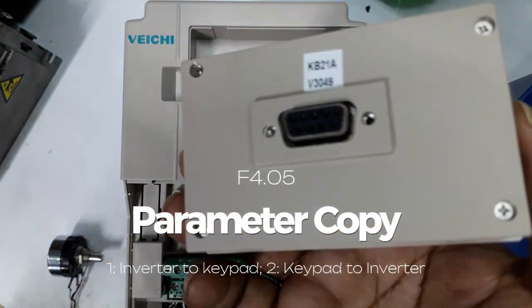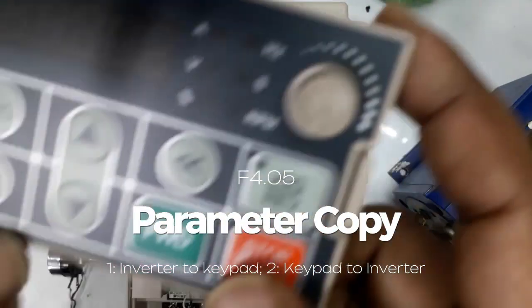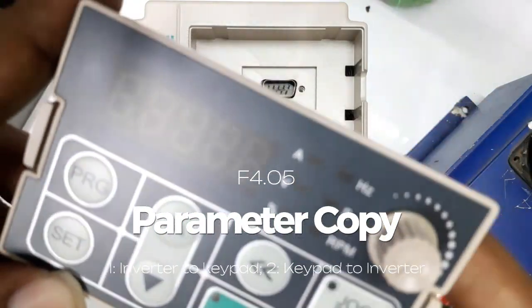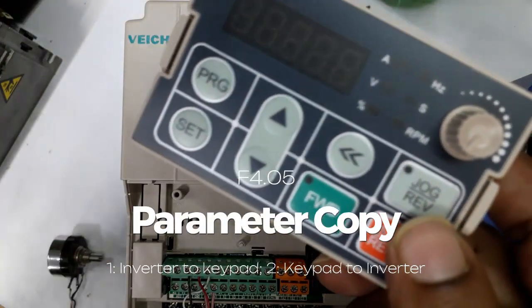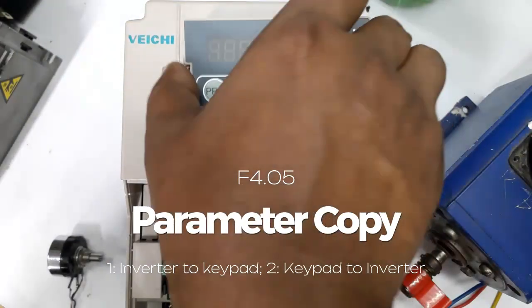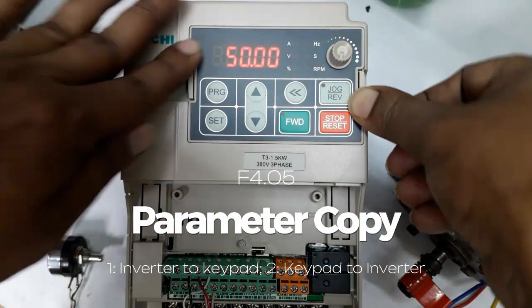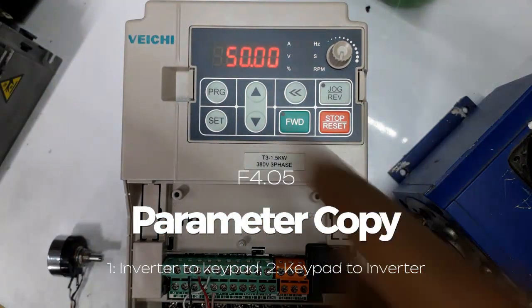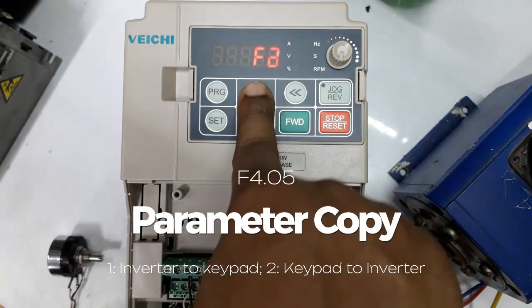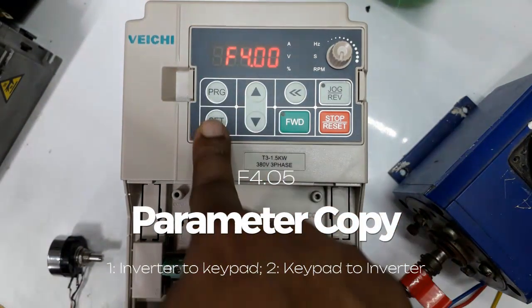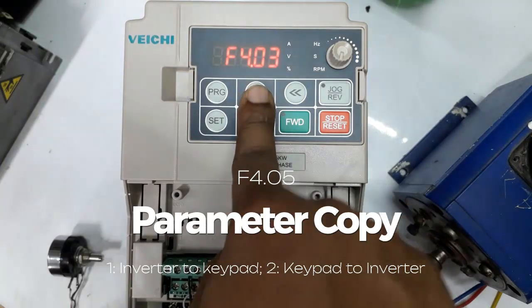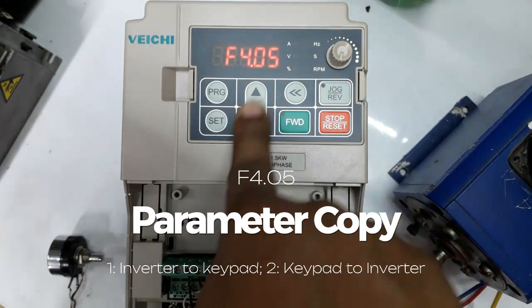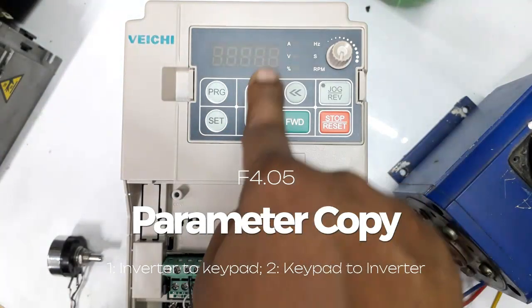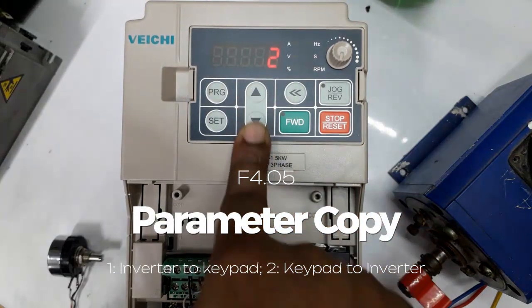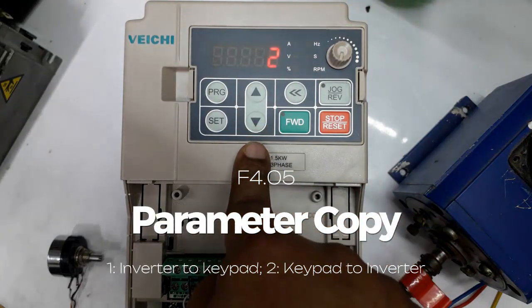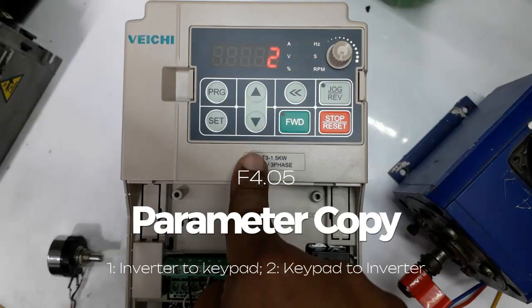This keypad you set in another drive and copy the parameters again from keypad or keyboard to inverter. Set parameter F4.05. Set 2 here. So setting this keypad in another drive, go to the parameter F4.05 and set 2 here to copy parameters from keyboard to inverter.